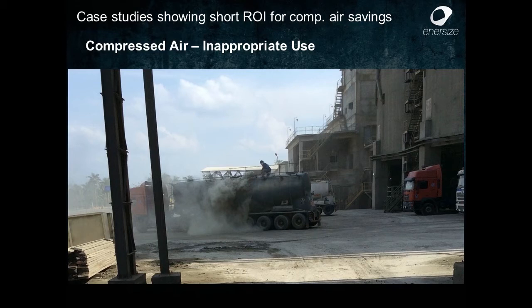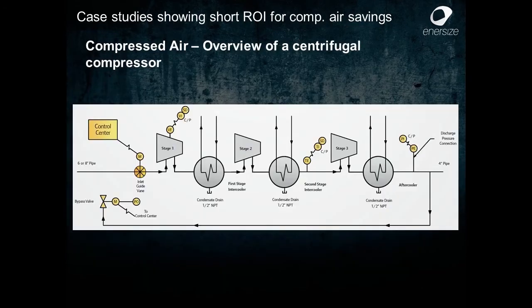The next slide is just to give you a quick overview of a centrifugal compressor and how it works, just to keep you involved in the next few slides. You see the control center, we have the inlet guide vane, we have different stages in the compressor, and after each stage we have a drain where we have to drain out water from the compressed air. And then we have the bypass valve, or the blow-off valve, that will protect the centrifugal compressor from going into what we call surge mode.